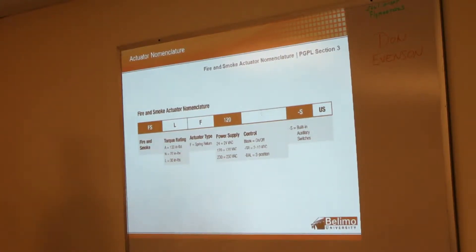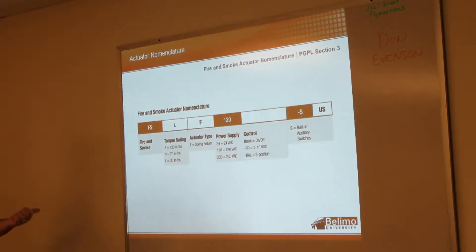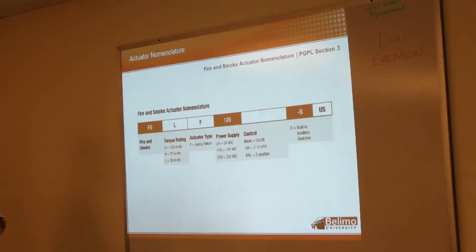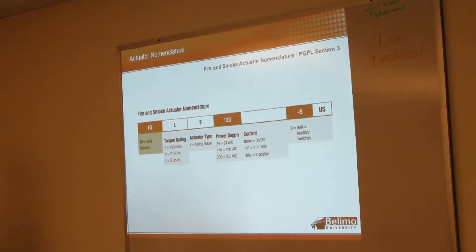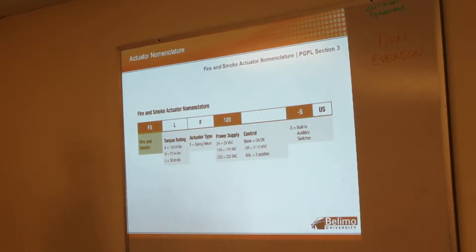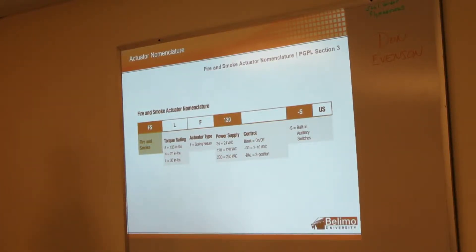The way to identify a fire and smoke actuator - they start with FS. That's fire smoke. These actuators have to have UL 555 and UL 555S approvals. All the ones that start at FS have those approvals.